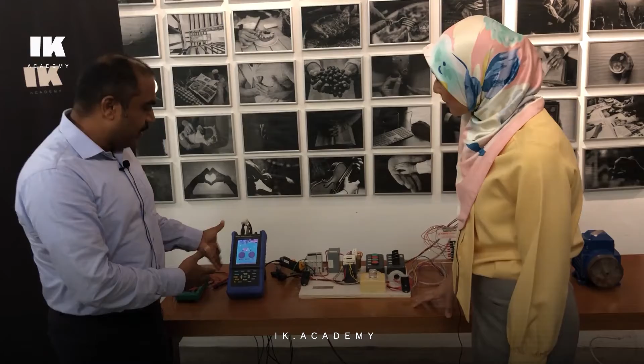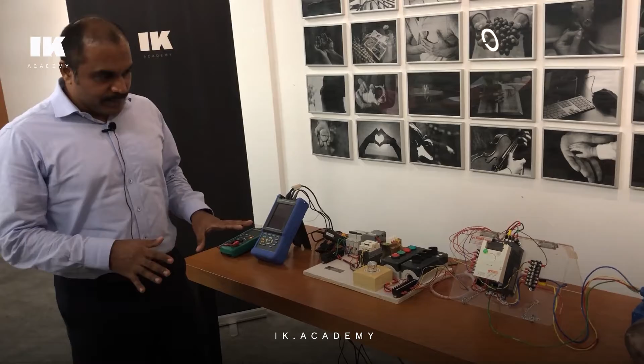Besides, of course, we have power measurement meters here, with which we can measure various electrical parameters, for instance the input voltage, input current, and not only that, the harmonics. Looking at the waveforms, the output waveform of the variable frequency drive, we can investigate what kind of waveform the motor is receiving using the power measurement meter. So these are the equipment that we have, which we can use to learn and demonstrate a lot of real-time issues that we face in the industries. Let's see what we can do with this setup.